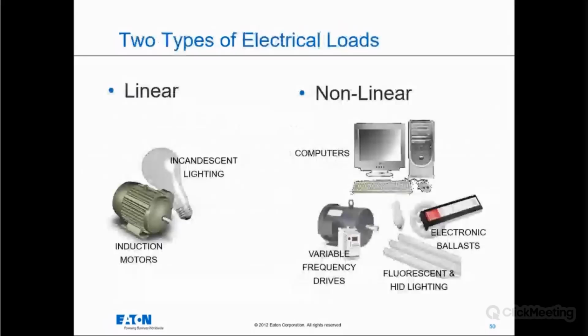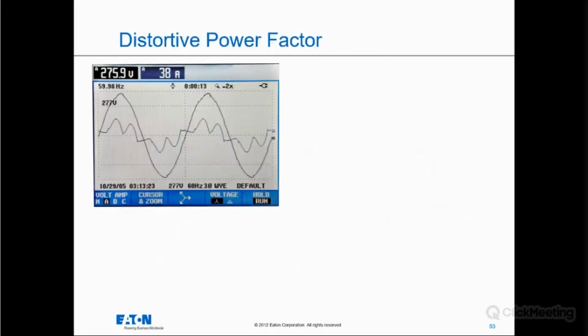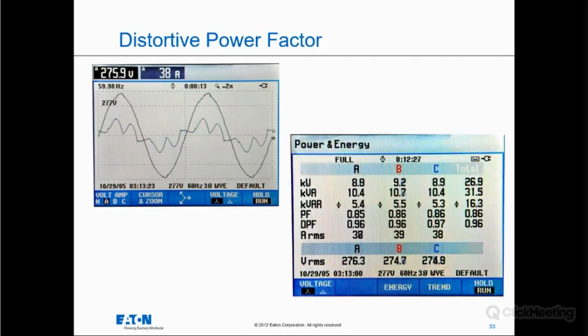What is distortion power factor? Again, it's coming from nonlinear loads, and it is distorting the waveform. And it also contributes. So you have two, and you need to know both of those: what your true power factor and your displacement power factor are. Why do you need to know that? Well, if you just looked at your power factor correction here, your DPF, you can see that's your displacement power factor. That is your inductive motor load power factor. So the DPF, the displacement power factor, is actually pretty good in this example.